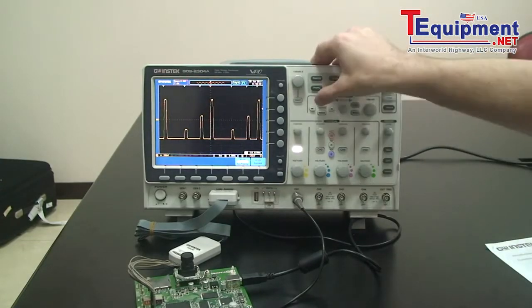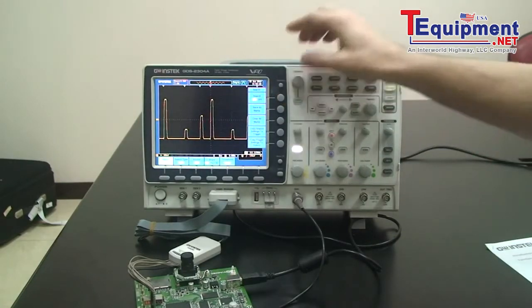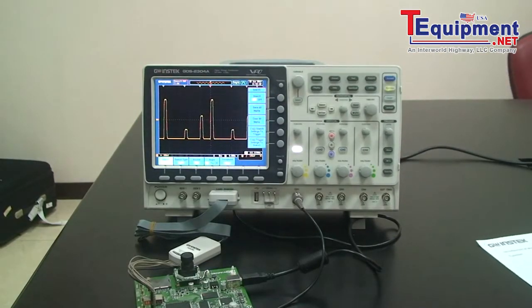To use the search function, just press the search key and turn search on. The search conditions are fundamentally the same as the trigger conditions. However, the search function uses the measurement threshold levels rather than the trigger level.